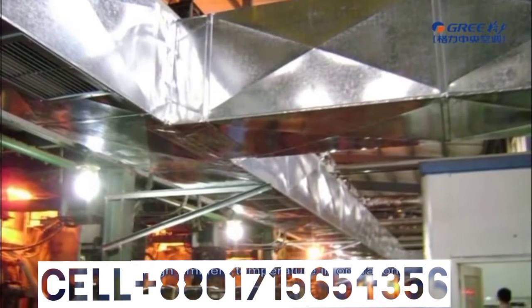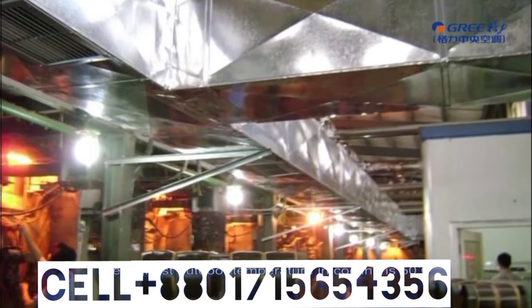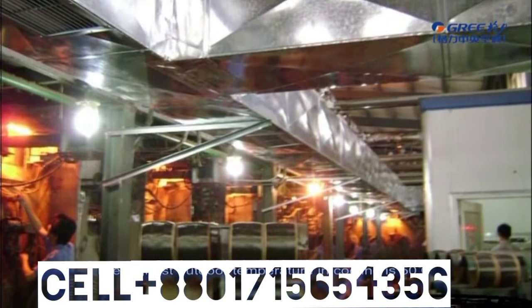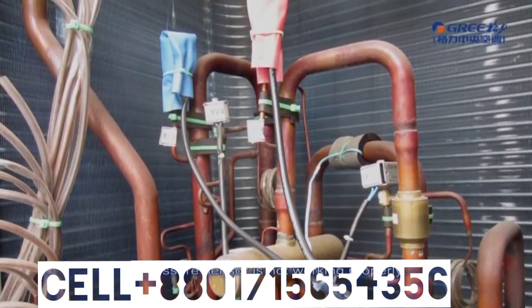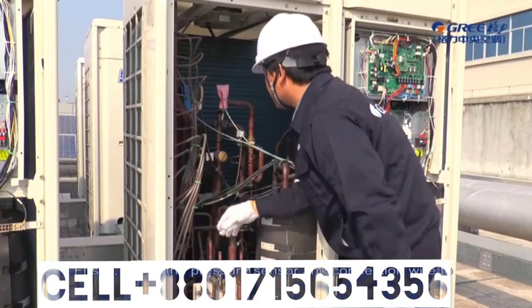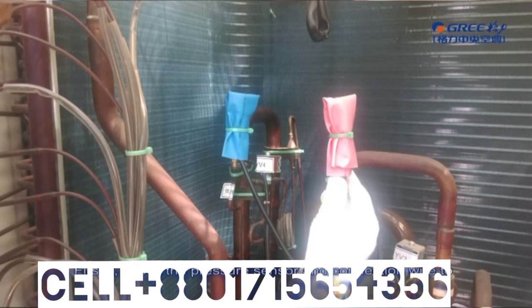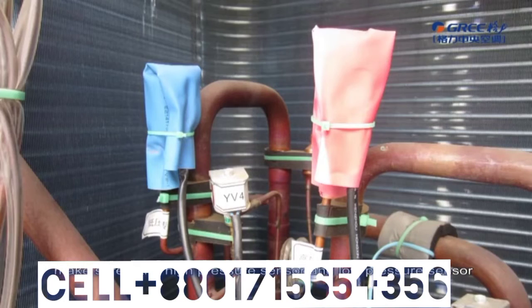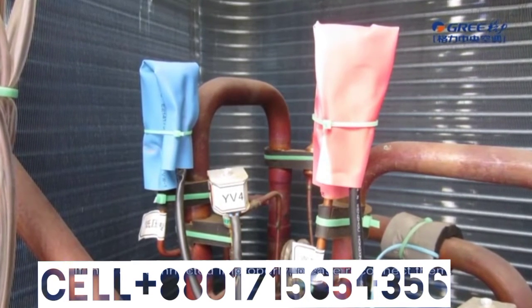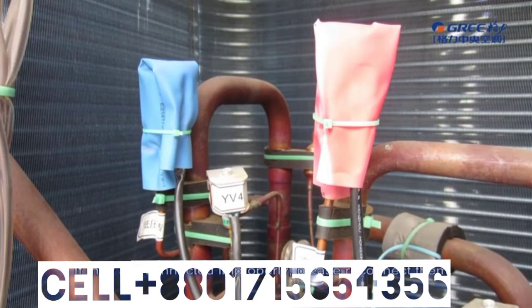3. High ambient temperature in operation. The highest outdoor temperature in cooling is 50 Celsius degrees, and the highest indoor temperature in heating is 30 Celsius degrees. When the actual ambient temperature exceeds the limit, protection may appear, which is a normal phenomenon. 4. Pressure sensor is not working properly. Firstly, check the pressure sensor and connection wire to make sure the high pressure sensor and low pressure sensor are connected properly. If they are connected improperly, please reconnect them. If they are connected properly, please check if the high pressure sensor is in good condition.